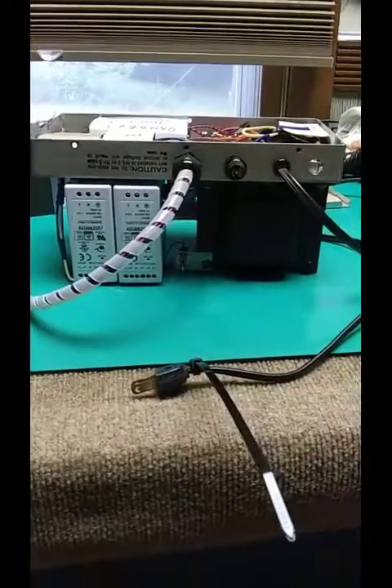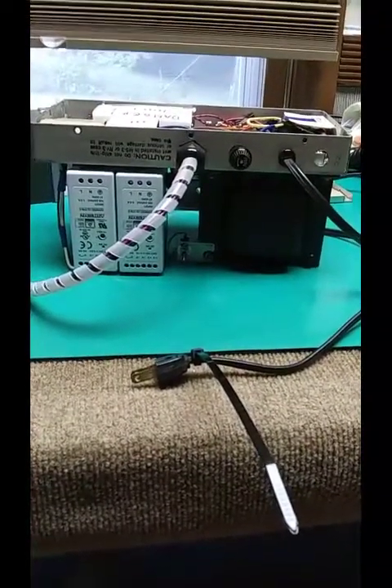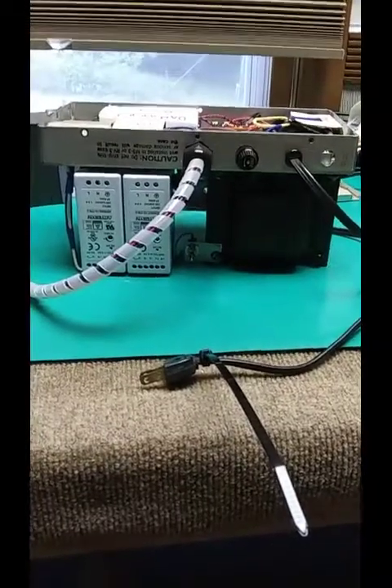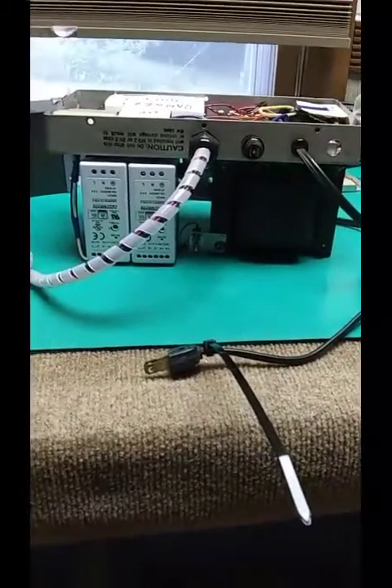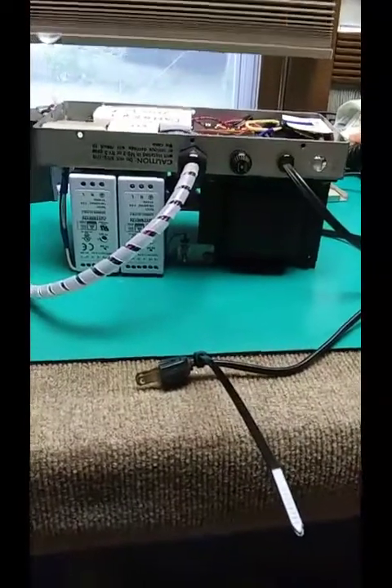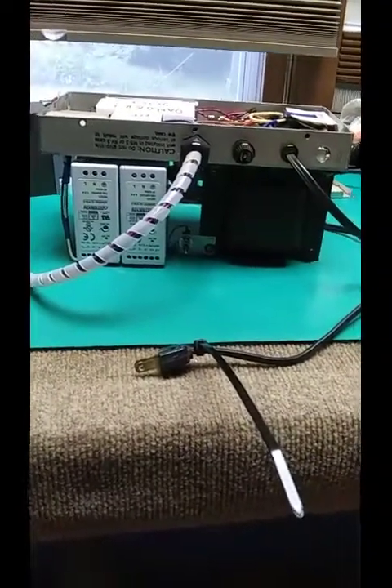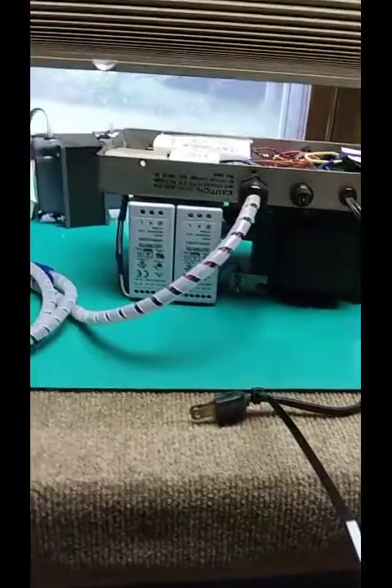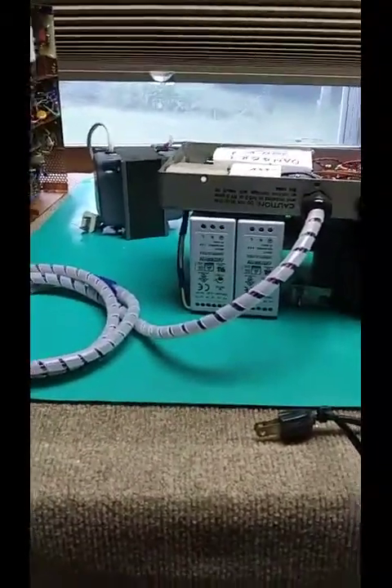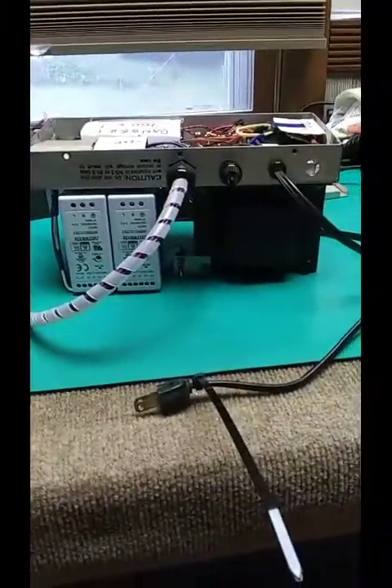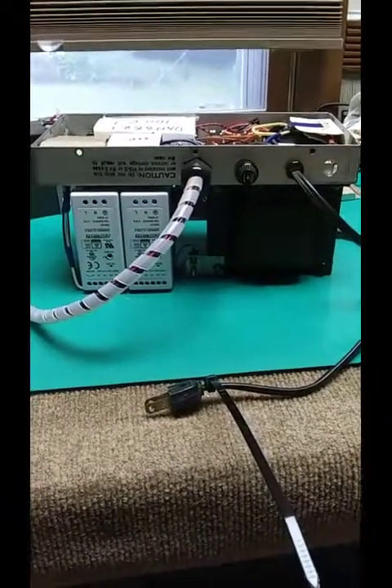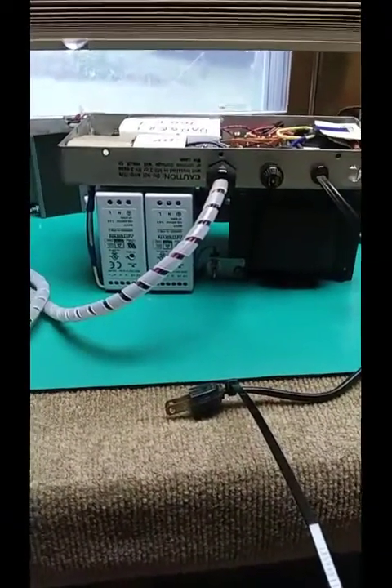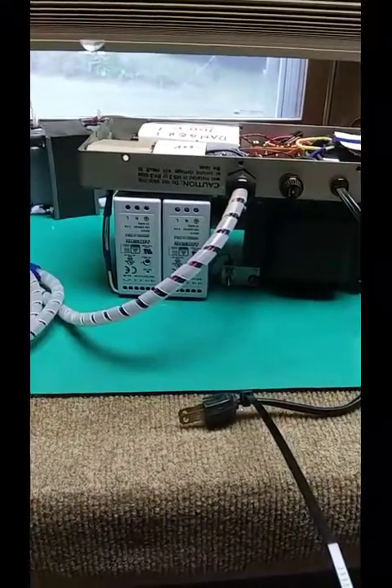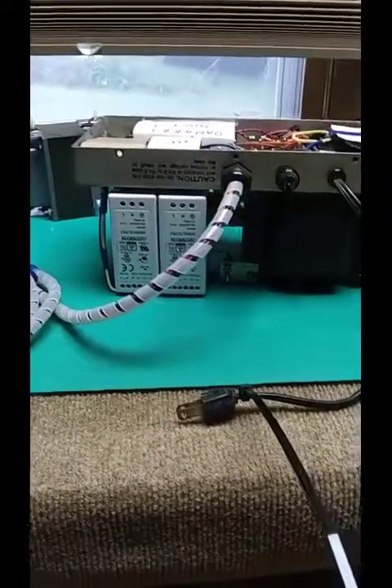This equipment came from the days before we had grounded outlets for the most part. This is back when electronics used high voltage. Those high voltages are dangerous, can kill easily. So universally, this older equipment was heavily shielded. The high voltages kept within real good chassis, occasionally within plastic chassis, along with the concept of double insulated, so the user can't contact anything energized without going to some trouble to take it apart.